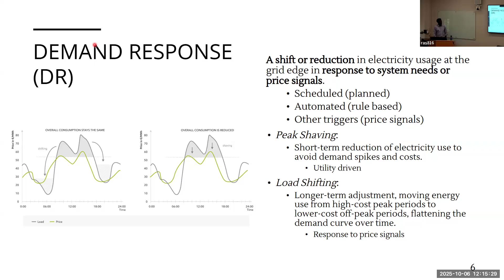You can have these devices scheduled, like day-ahead planning where you run power flow or simulation to see what the grid will look like the next day, using weather data and other grid information, and plan a demand response. You can automate it, so if a substation or circuit breaker reaches a certain capacity or power rating, you can automatically execute a demand response. Other triggers, like load shifting, can be done through price signals. If you increase the price at peak, the customer is incentivized to charge their car or batteries during off-peak hours and discharge during peak because it makes economic sense.